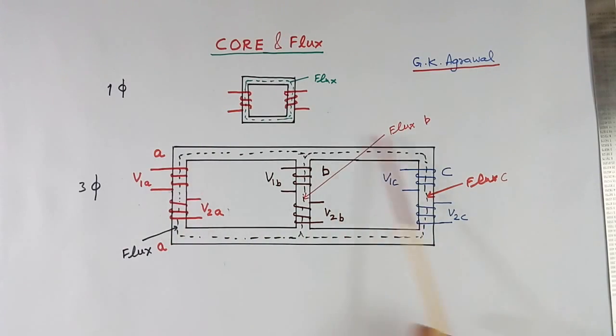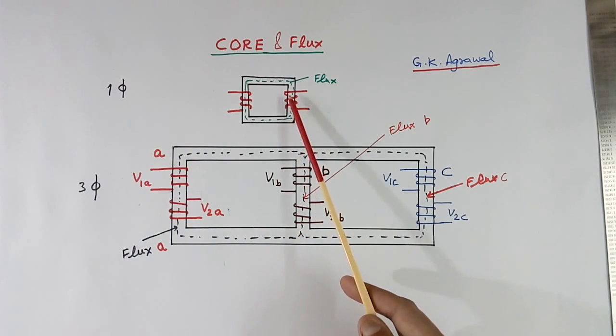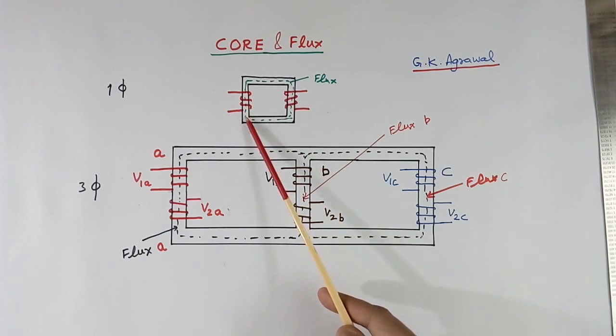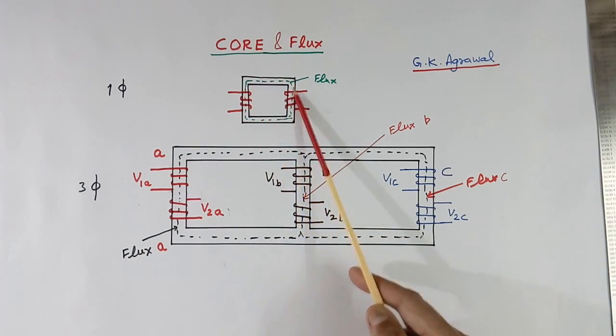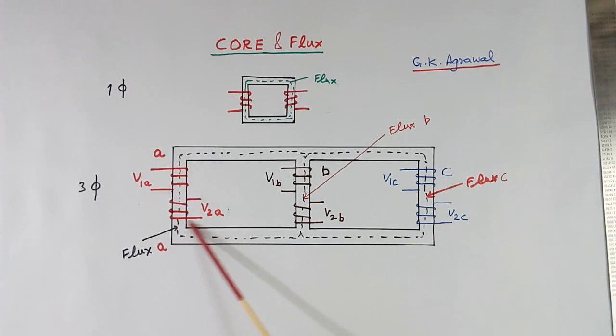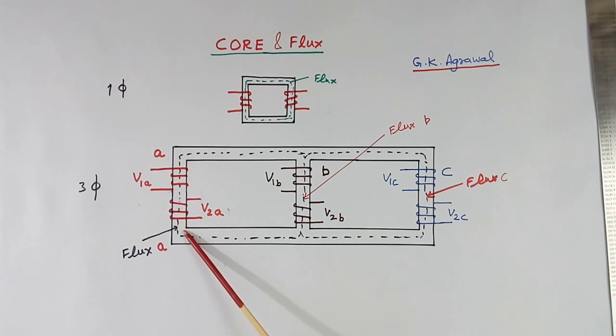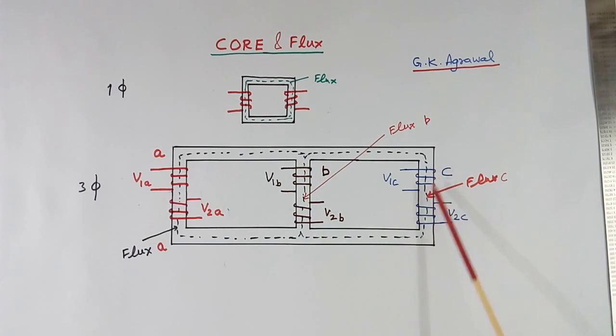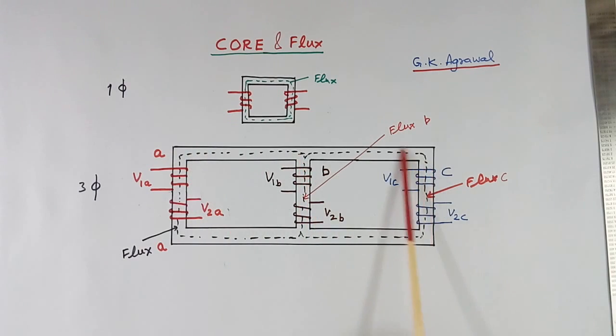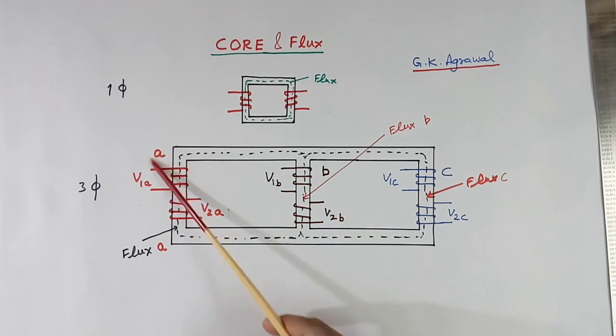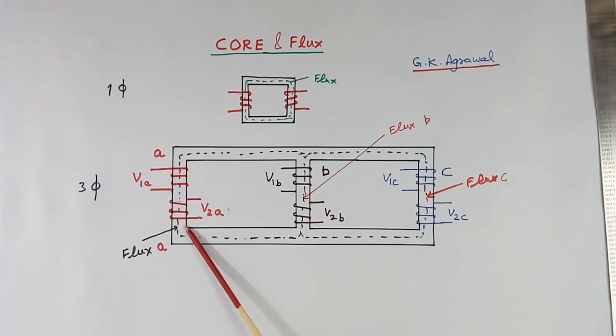This is the core and flux diagram. The black color is the core, and the dotted line is flux. In a single-phase transformer, primary and secondary share the same flux. Similarly here, for phase A, this is the primary winding and this is the secondary winding, so flux is common. Similarly in each phase, both winding fluxes are common. But flux here and in another phase is not the same, because each phase flux links its own limb. So flux in one phase — in both windings — will be equal, but flux of all 3 phases will be different.